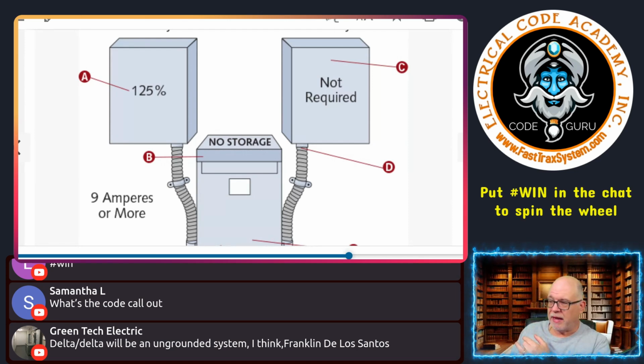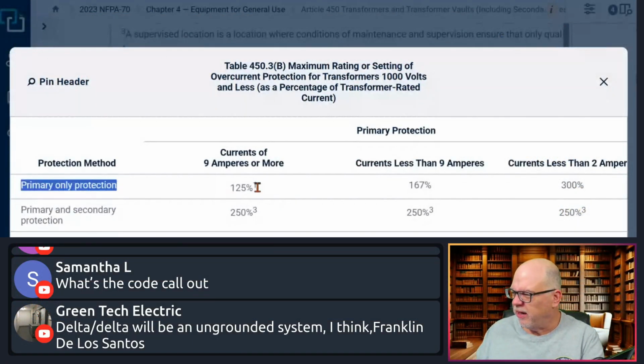So I'd take whatever my amps value was when we took the kVA divided by the voltage on the primary side. I would take that at 125%, and I would try to size my overcurrent protective device. Again, no requirement yet for this transformer's secondary protection, just primary only protection to protect it in this scenario. So it's 125%. That's what you see on this table. And then when we said you can go to the next size up if it doesn't correspond, that's where this 1 comes from.